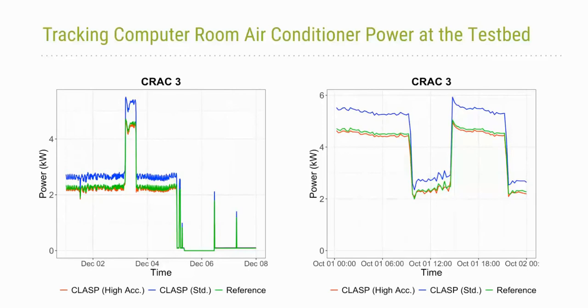I think they're down in like the 0.6 range. Usually we want power factor up at kind of 0.9 or higher. These have low power factors just due to the nature of the device. And with the standard accuracy CTs, that phase angle error introduces an error into the power calculation.